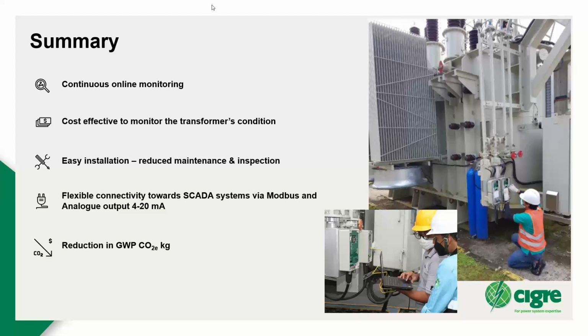Actually, if you take a sample and bring it into the laboratory, it has another temperature. And automatically, of course, it has another relative saturation. The point is also that if you take a sample out of a transformer, you don't have solid insulation inside. The relative saturation and these recommendations, which you saw in the presentation, are valid when you have the system of solid insulation and oil, and this is only in the case of a transformer. So out of a transformer, it is very difficult to make a real judgment on relative saturation, because the conditions are different.